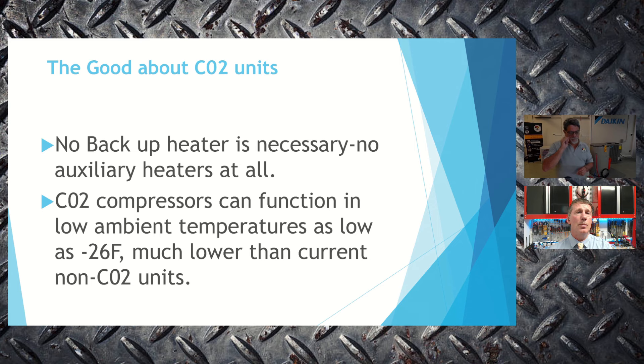There's no backup heat in this monoblock system. Unlike many hybrid tanked water heaters that use a small heat pump BTU capacity alongside electric resistive elements — typically 2,500 watts or 4,500 watts of supplemental energy — with a monoblock we design the entire heating load into the one unit. The heating capability is fully integrated, so we're not relying on supplemental resistive heat.